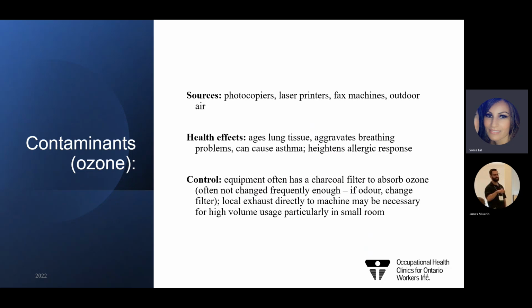Wherever you have a printer, or even the large scale printers, you must make sure that room or area serving folks for printing is exhausted, with fresh air supplied specifically for the printer itself. That's often missing in workplaces we've visited. As per the slide, equipment often has a charcoal filter to absorb the ozone, but it's not changed frequently - so there we go back to maintenance and lack thereof. Local exhaust directly to the machine may be necessary for high volume usage, particularly in a small room. Those are the controls required for this type of office equipment.